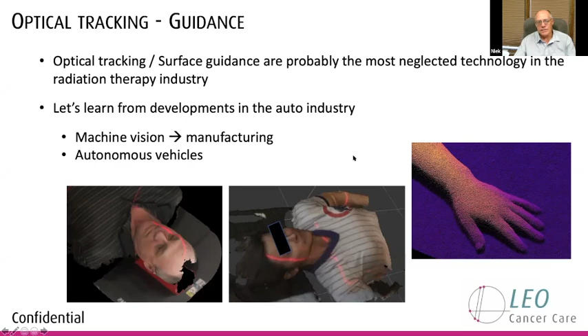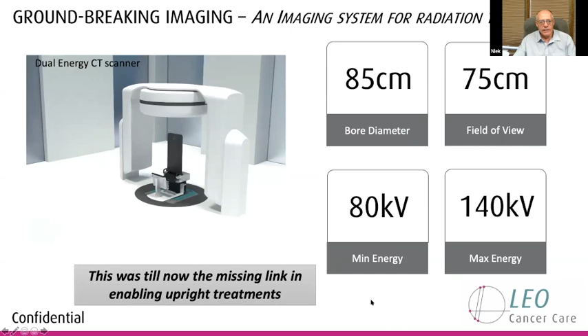If the patient goes in, you can see how the backrest is synchronized with the scan angle, and we can see the scanner ring just comes down and goes back up. This scanner ring is fully counterbalanced, so one can actually deploy it just by hand. The technical parameters are a 75 centimeter field of view, and it will be dual energy right from the beginning. So this device was actually the missing link in enabling upright treatments.